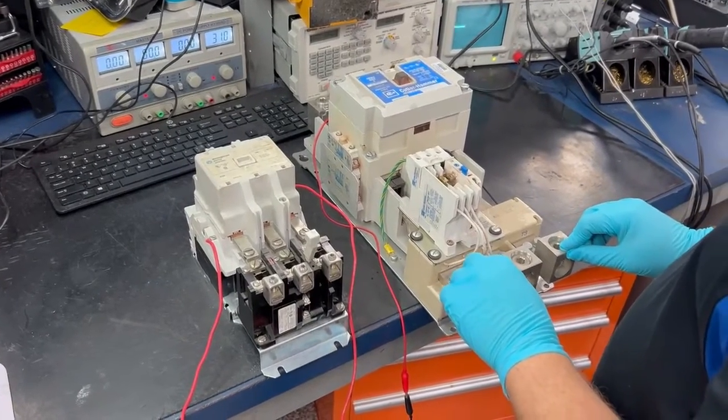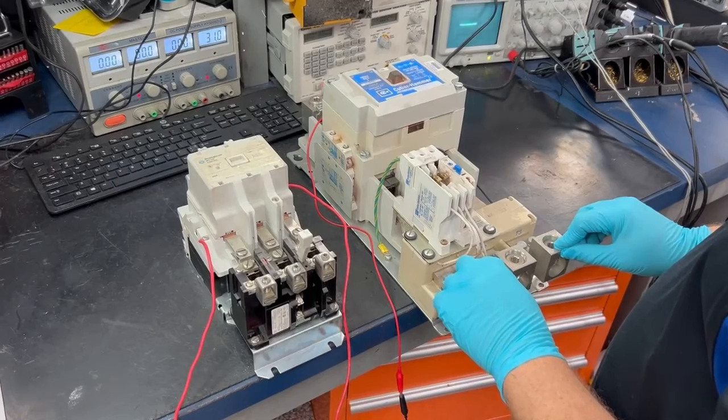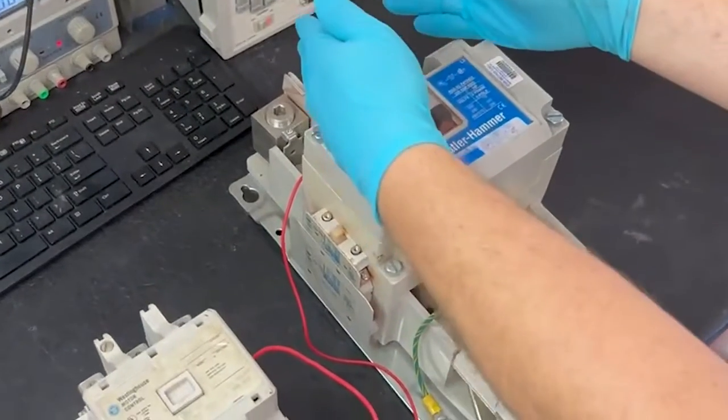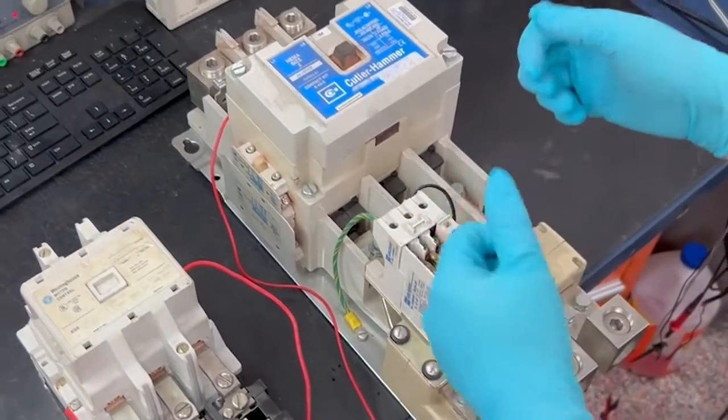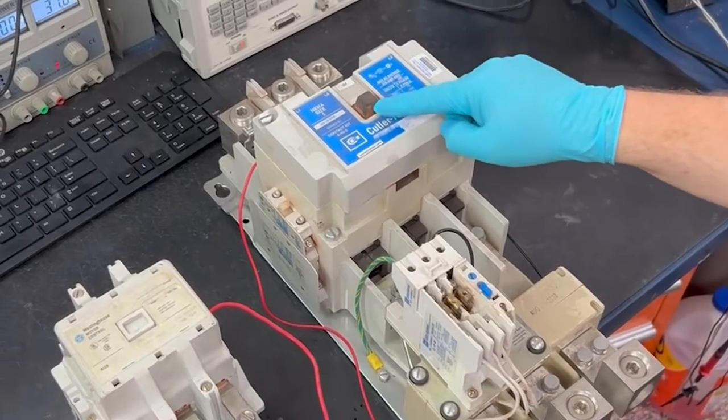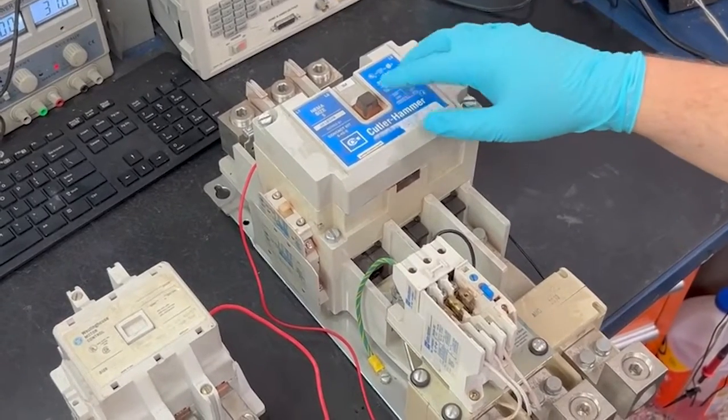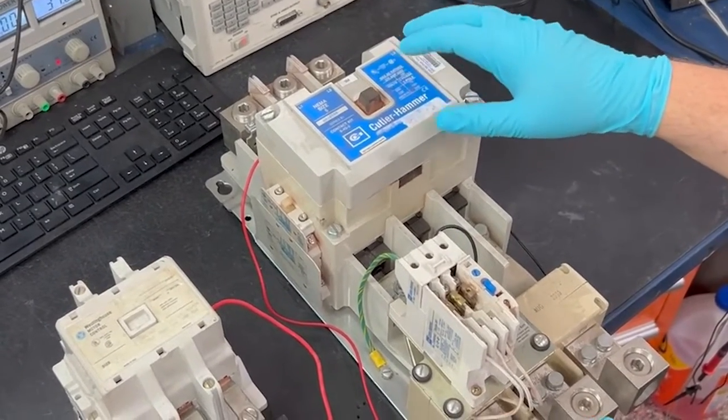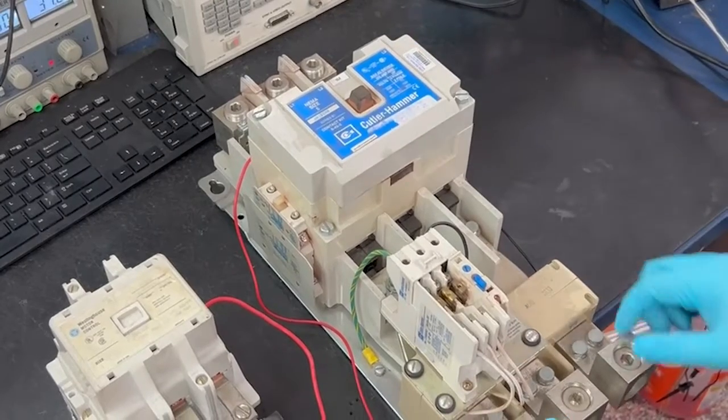We will show the mode of failure that many report as chattering. Chattering happens when the contactor tries to pull in, allowing power to pass. Rather than make complete contact, the contactor will be noisy, creating a lot of vibration and chattering. We will now demonstrate that.